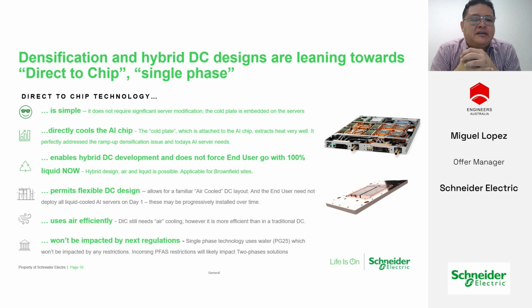A little bit complicated, but it can be done - you could have one server or rack with full liquid cool hardware deployed adjacent to another server with air-conditioned, non-AI-ready servers. They could be side by side, or segregated into separate rooms. Customers tend to segregate them where there's a need for co-location of liquid cooled servers or racks, intentionally designing islands of floor area designated with liquid cooling. Nevertheless, the entire data center is thus labeled a hybrid data center - a combination of air-cooled and liquid-cooled servers.